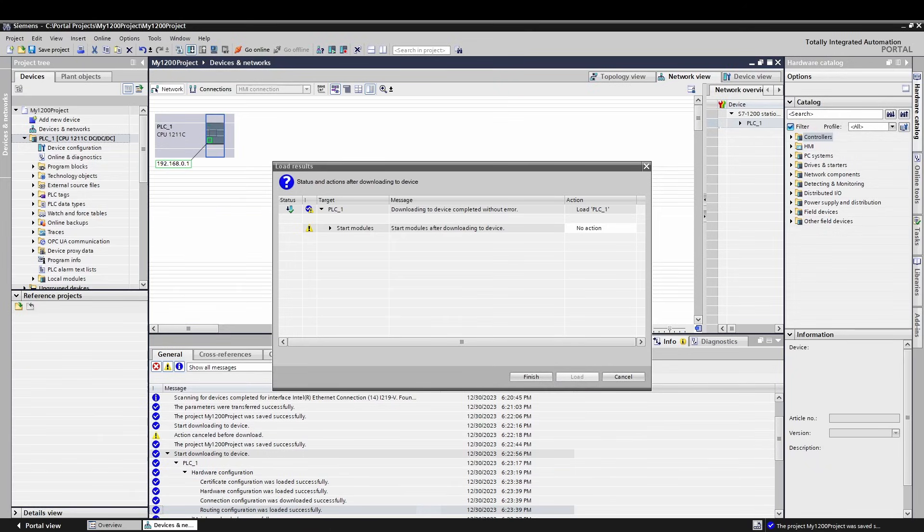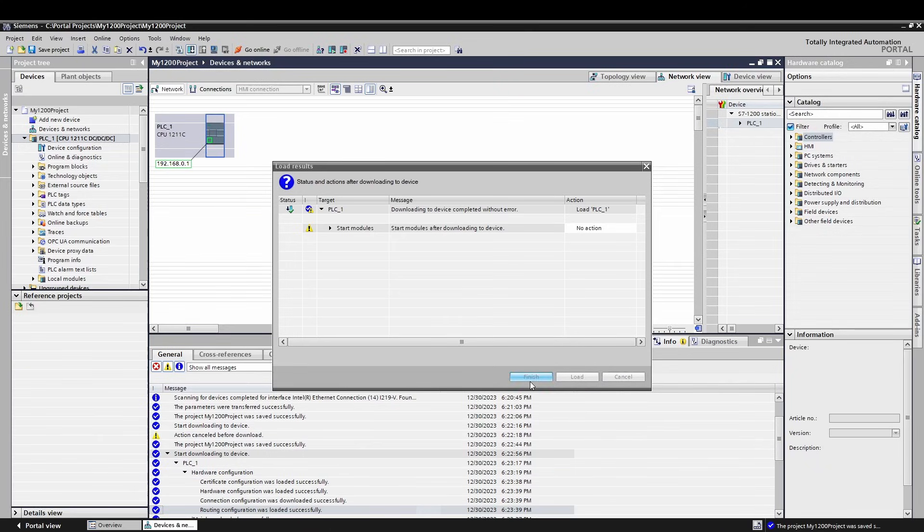There are two things that could cause issues here. First, your computer may not be on the same subnet. Yes, Portal can see across subnets, but when you go to download them, it uses a regular TCP connection, so subnet rules apply. Make sure you are on the same subnet and try again. Second, the device in the project may not be the same firmware as the real device.